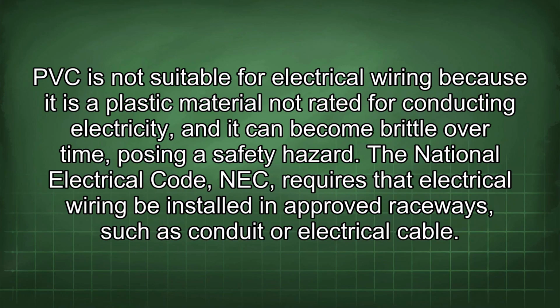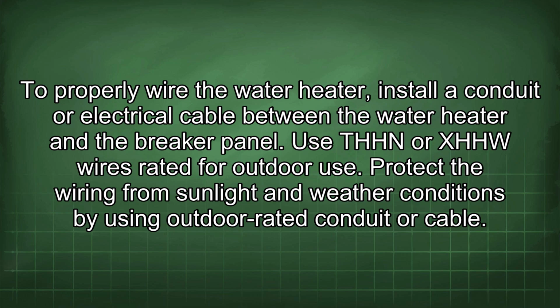PVC is not suitable for electrical wiring because it is a plastic material not rated for conducting electricity, and it can become brittle over time, posing a safety hazard. The National Electrical Code (NEC) requires that electrical wiring be installed in approved raceways, such as conduit or electrical cable. To properly wire the water heater, install a conduit or electrical cable between the water heater and the breaker panel.